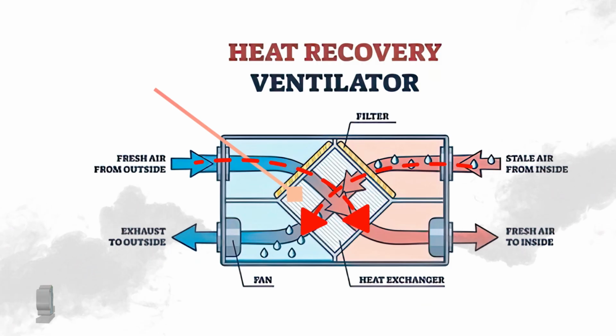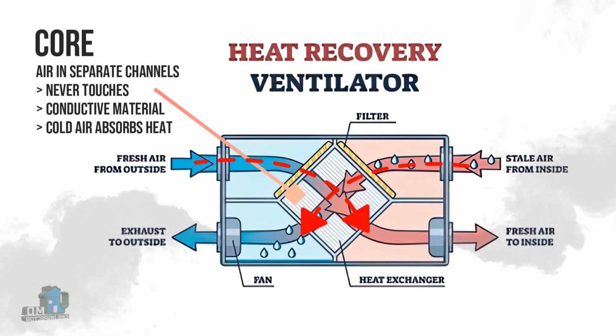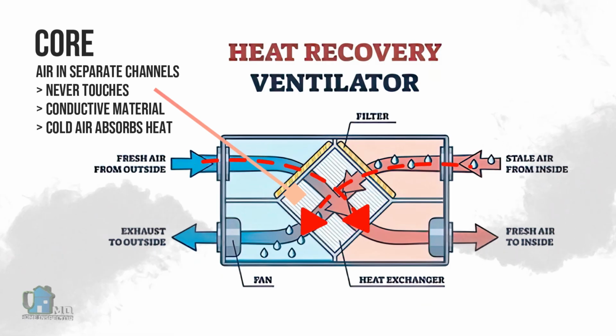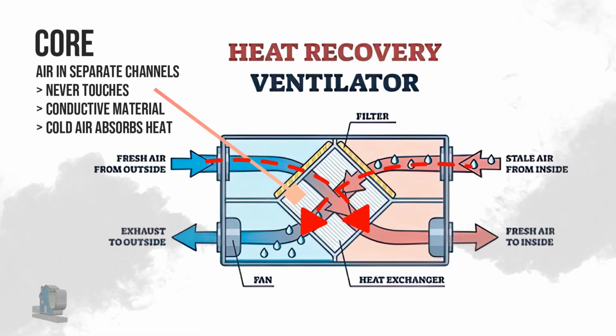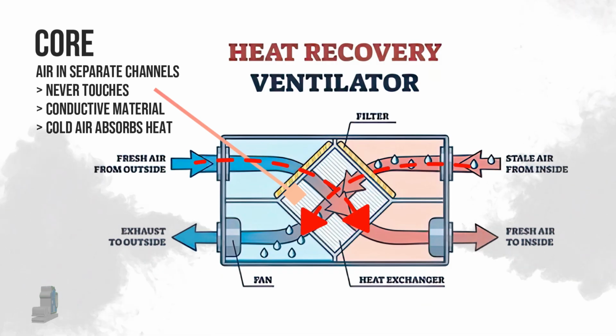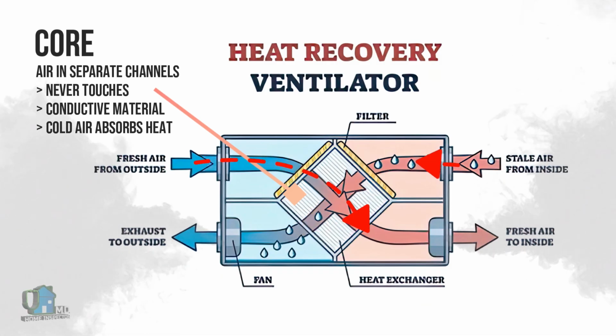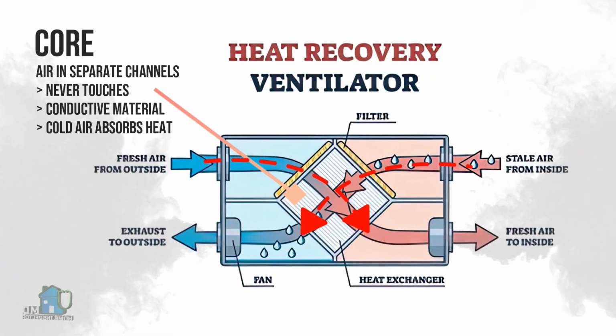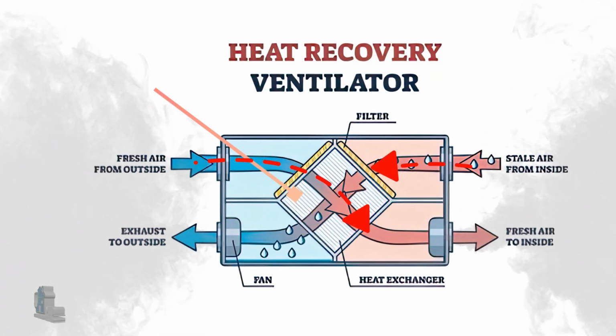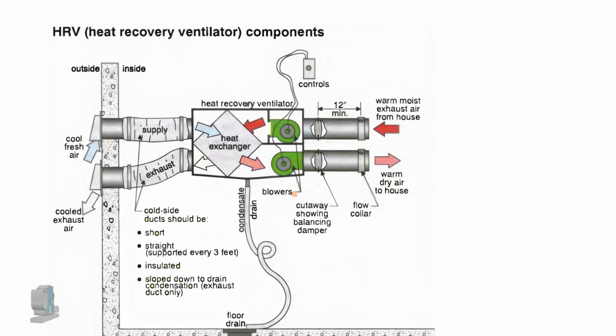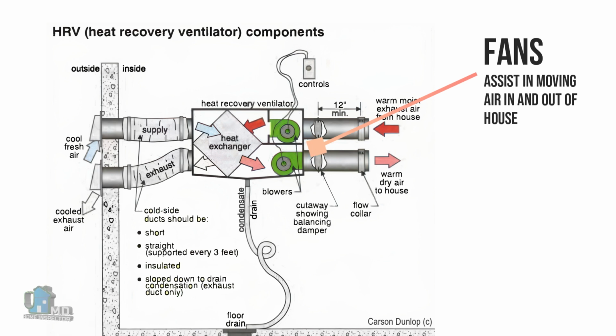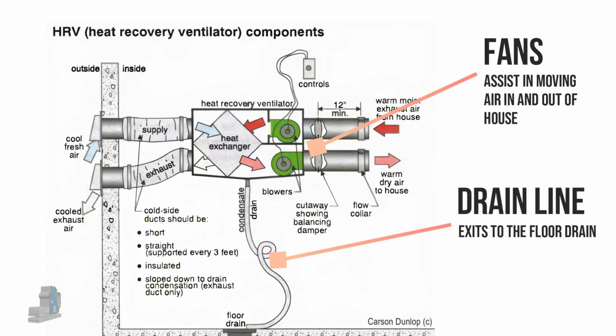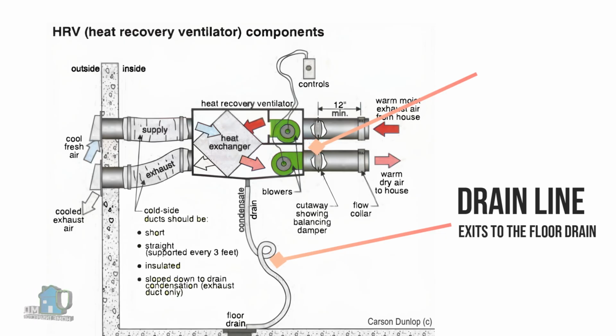In the heat exchanger, the warm air from the house is warming the cool air from outside. So now you have warm, fresh air entering the house, and that's the key. Remember that the warm house air and the cool outside air do not come in direct contact with each other in the heat exchanger. Other parts of the system are fans to assist in moving air, and you also notice a condensate drain line coming out of the cabinet and most likely exiting to a floor drain in the basement. That's because this device produces water from the core.